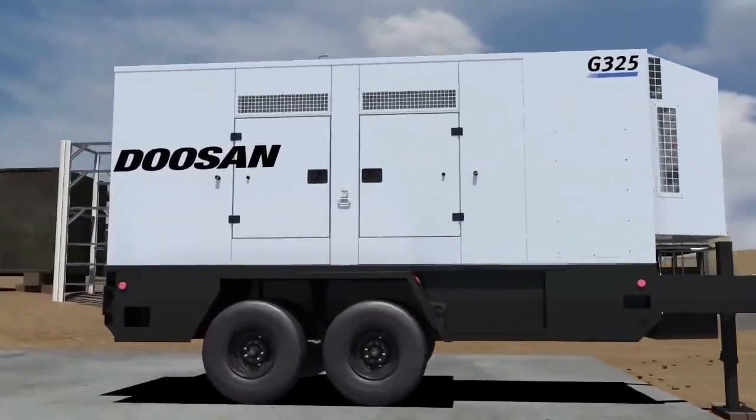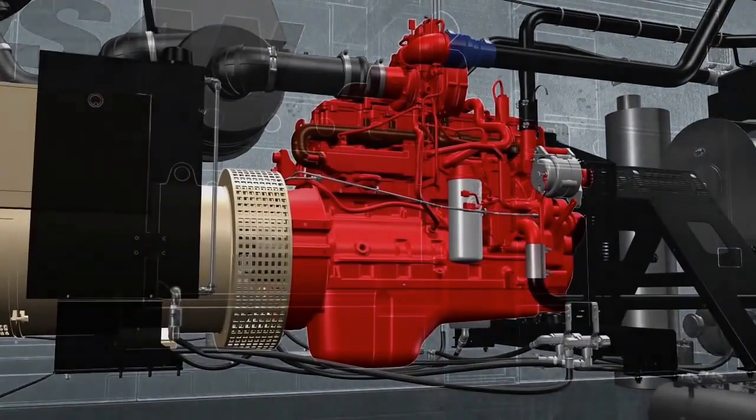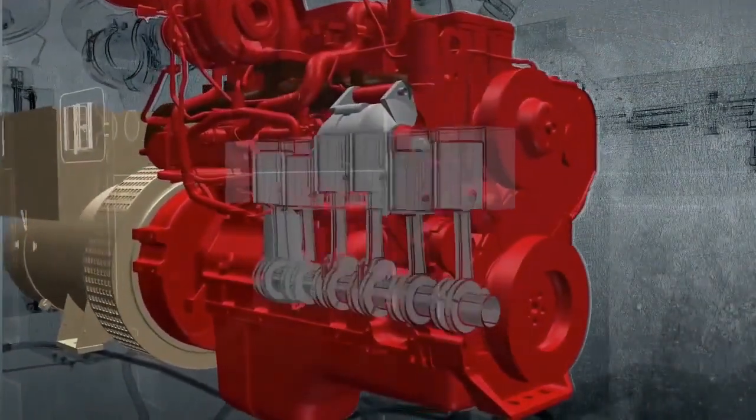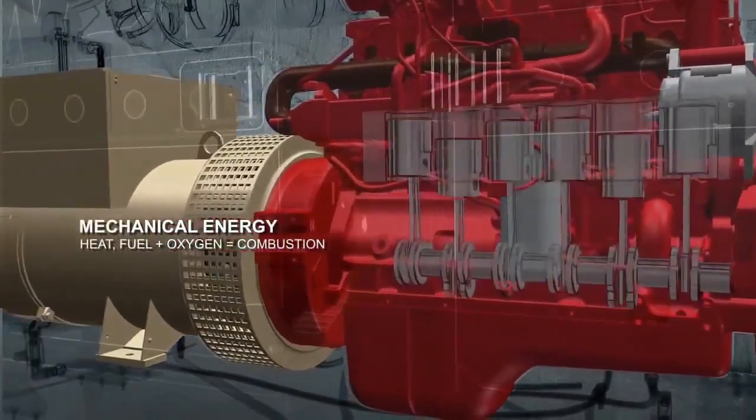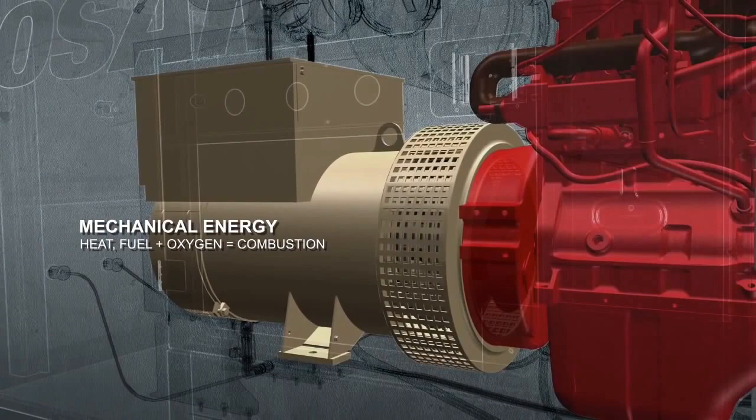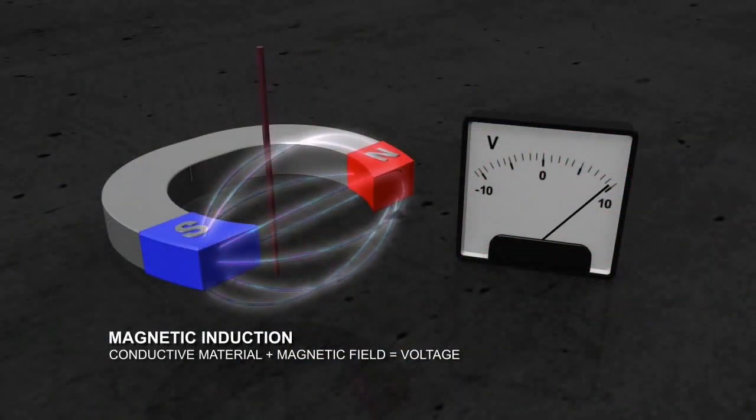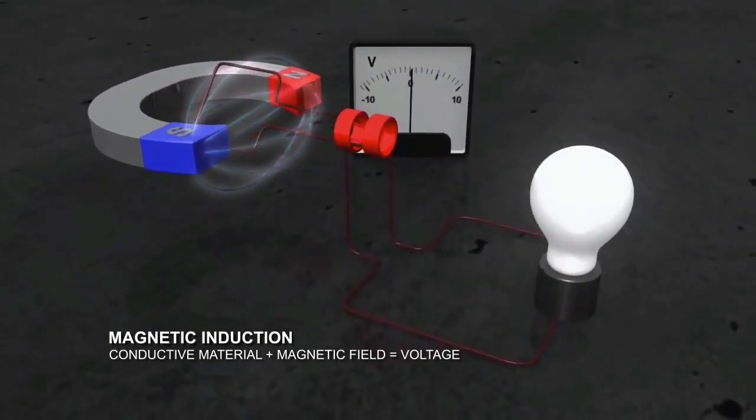A generator engine converts diesel fuel to mechanical energy that rotates the crankshaft. As combustion occurs in each cylinder, energy transmits to the engine crankshaft, which generates mechanical power for the alternator. An alternator converts mechanical power into electrical energy in a process called magnetic induction. Magnetic induction occurs when a conductive material, such as a copper wire, passes through a magnetic field and voltage is produced. If the wire is connected in a complete circuit, the power can be transmitted.